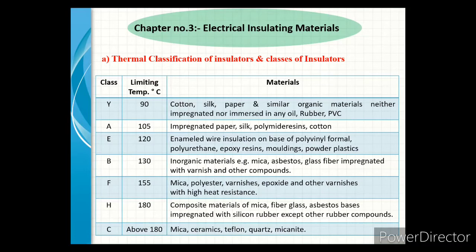Class A has a limiting temperature range of 105°C. Materials included are impregnated paper, silk, and cotton. Class E has a limiting temperature range of 120°C. Materials included are enamel wire insulation based on polyvinyl formal, epoxy resins, moulding powder, and plastics.